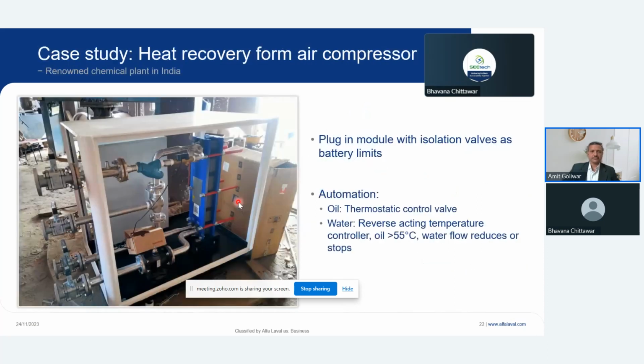To explain in more detail, this can be a heat exchanger with an oil and water line. This is typically the oil line, and only if the temperature of the oil is more than 55 degrees will it go to the heat exchanger. Otherwise, it will come to the return line, and water will come from the other line, and you can generate hot water, and this will reduce the fuel consumption in the boiler.